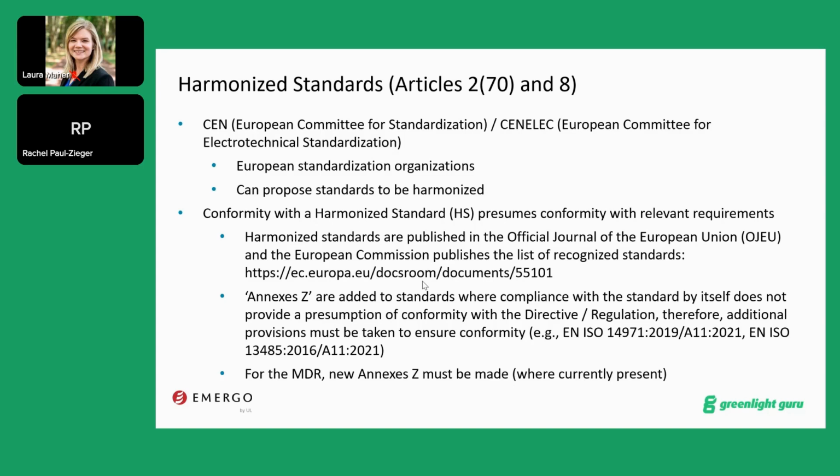You have the example of Annex Z in the standard for risk management, 14971, or for quality system in 13485 standards. And obviously, for the MDR, new Annex Z must be made. It was done for the MDD, but now it has to be created under the MDR.